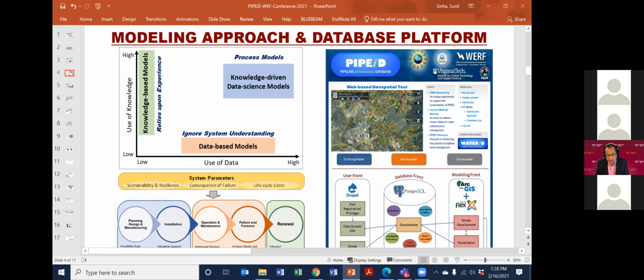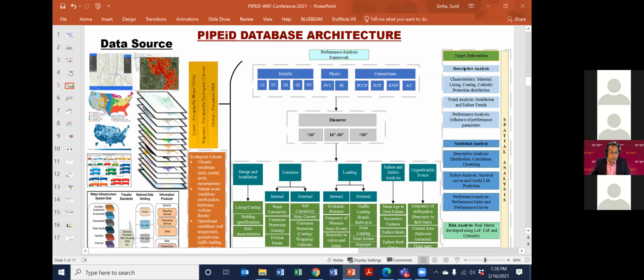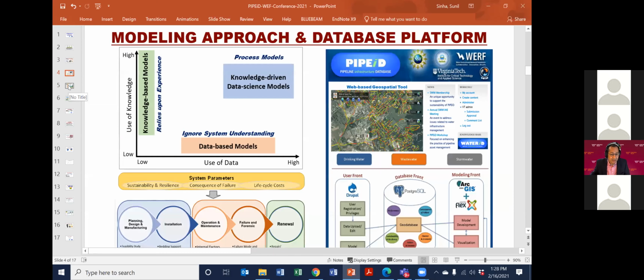Their pipe isn't failing because the soil is corrosive, it's metal pipe and the soil is actually fine. But when we did correlation analysis, we found the pipe is tuberculated. They claim it's a 12-inch diameter pipe, but the internal diameter is not 12 inches, it's hardly 4 or 5 inches. So they're better off replacing that pipe, even if it isn't failing, because it's like clogged arteries. The pump runs all the time and it's not energy efficient.